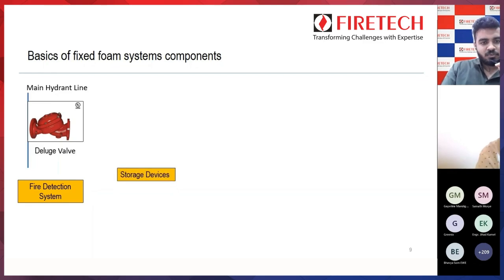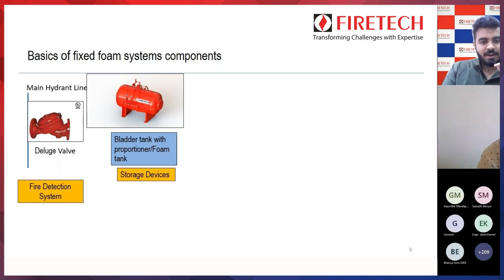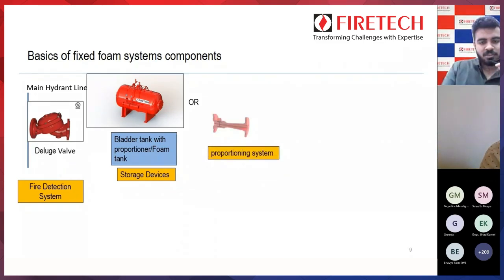Second is the storage device. In storage device we have two types: one is a bladder tank type and the other is a foam tank type. The bladder tank is not only a storage device, it is also a proportioning device. With the bladder tank there is no need to use any other proportioning equipment — your ratio controller comes pre-piped with the bladder tank. Third is the proportioning system.